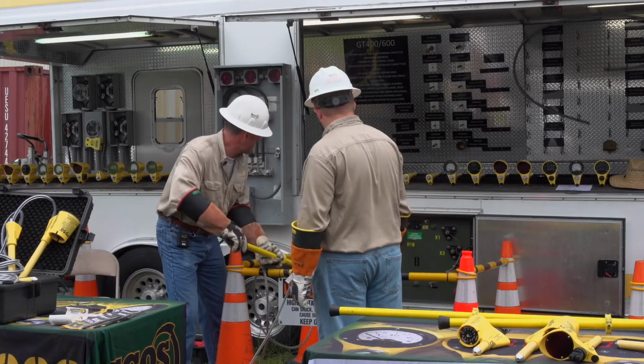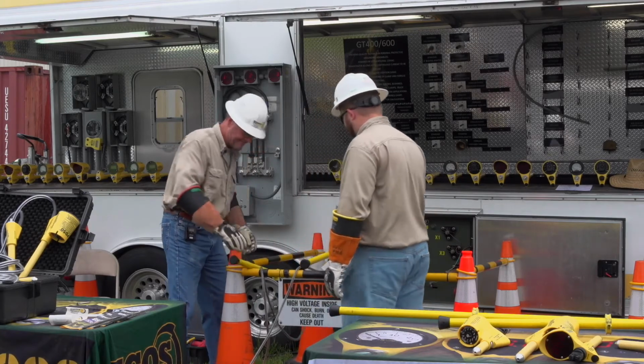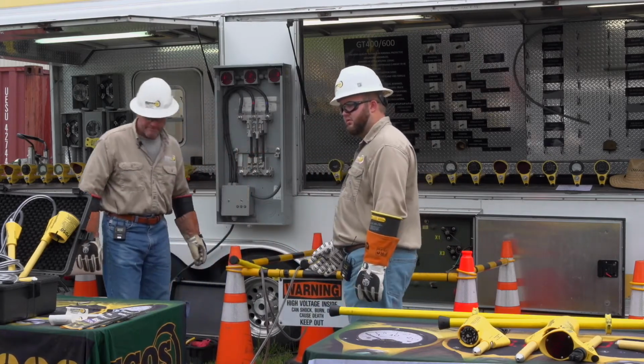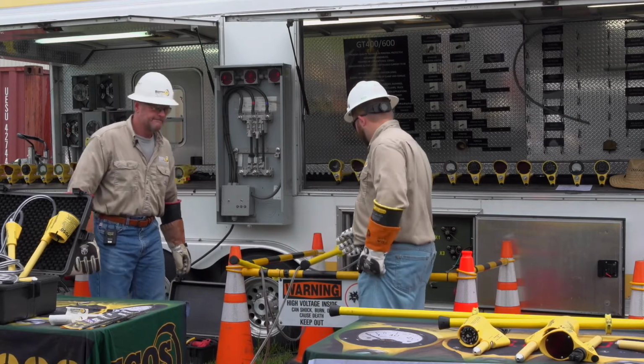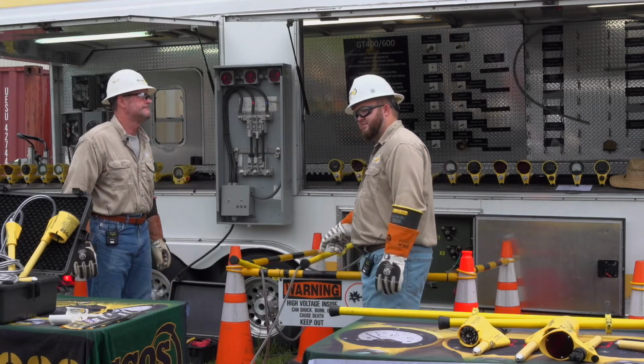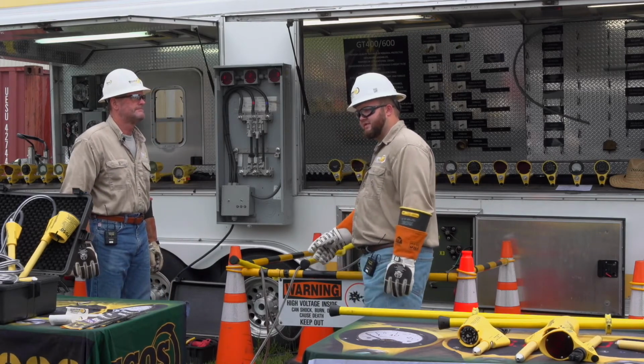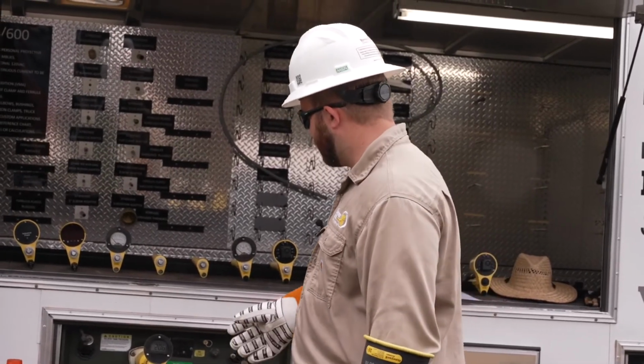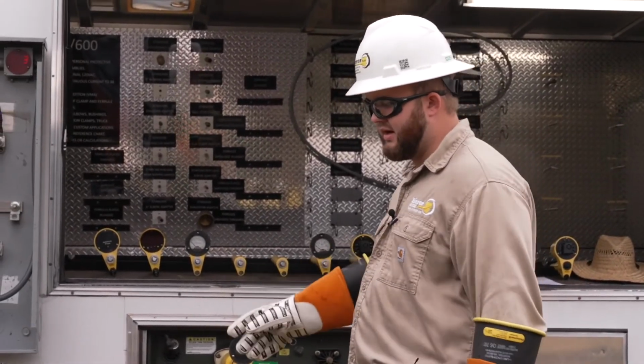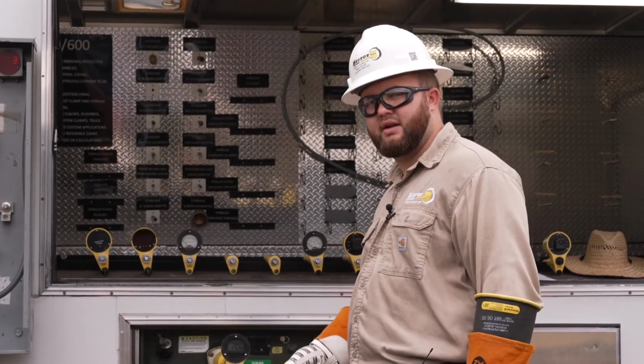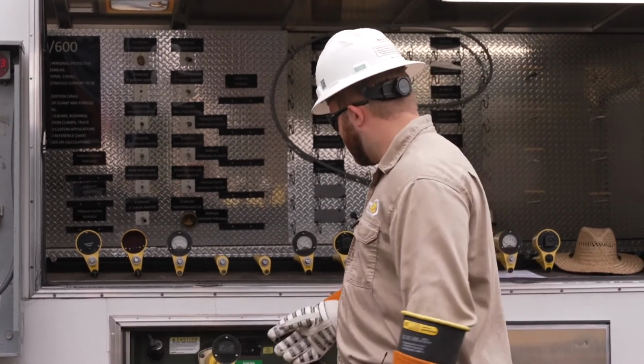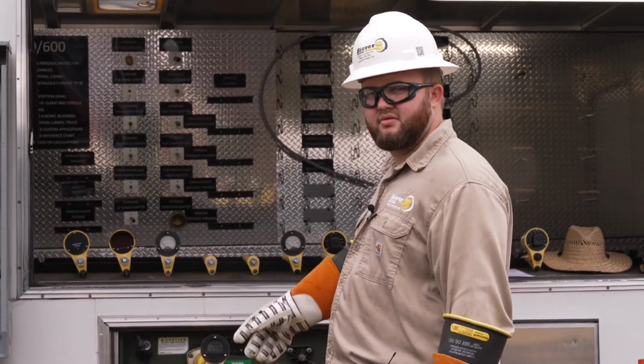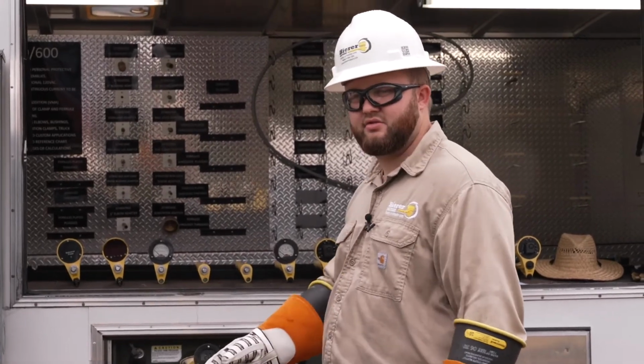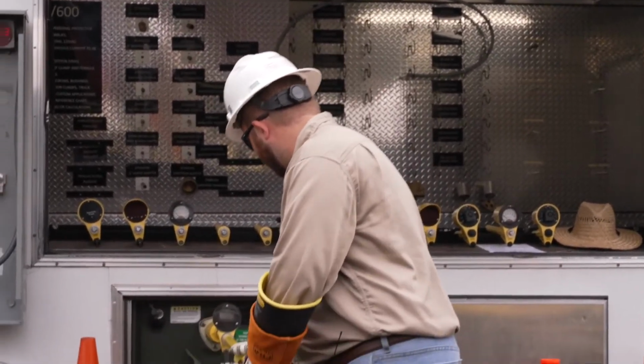Okay, explain to them what we're doing, Ryan. So anytime you're phasing with a corded tool, or maybe high potting, you always want to discharge the capacitance between the two devices through the cable. So we're always going to go with the second probe to ground. You don't have to do it in that order, but we recommend doing it that way so you can physically see the numbers draining, that potential draining between the two devices.